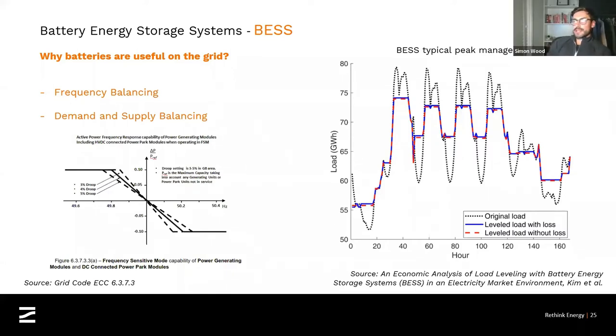Yeah, we touched on this earlier, but it's just to build off the back of having briefly explained exactly what constitutes a battery energy storage system. It's about understanding why exactly these are useful on the grid. We mentioned that the typical use case, as most people understand battery energy storage, is that it stores energy when there is a surplus on the system. So if we've got a very windy day and a very sunny day, and we've got an overgeneration of power, we could use batteries to store some of that energy. That could then be released at a time where demand on the network is higher. And that's essentially the peak shaving methodology, which is shown by the image on the right.